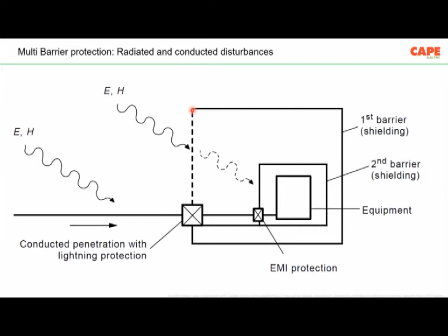If we have a good quality electrical building supporting modern electronic equipment, preferably concept 3 or 4 applies. This chart is from IEC 61000, concepts 2, 3, 4, and 5, which recommend this kind of protection scenario for buildings or electronic equipment in civilian facilities. So protection concept 4 or 3 is possible if we design and install our electrical and electronic installation, or design our building, with the aim to protect the electronics from such disasters of EMI.